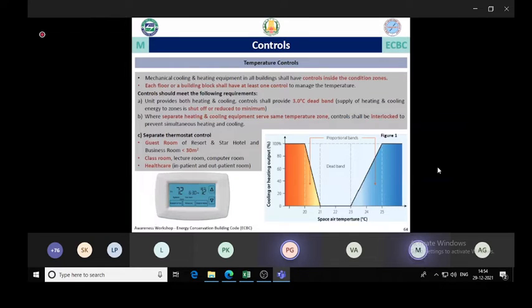Then another important requirement is the temperature controls. This is again a mandatory requirement. Each floor or a building block should have at least one temperature control. And similarly, each room in a hotel and any conference or meeting room within an office building, as well as office cabins which are less than 30 square meters, these kind of spaces should have separate temperature controls. So what we mean by temperature controls is either they should have individual separate indoor units by which we can control the air temperature, or if it's a centralized AC, then again we need to have something like VAV control, variable air volume controllers, to regulate the temperature. So this is one of the major requirements which could sometimes impact the HVAC design. This should be taken note of.